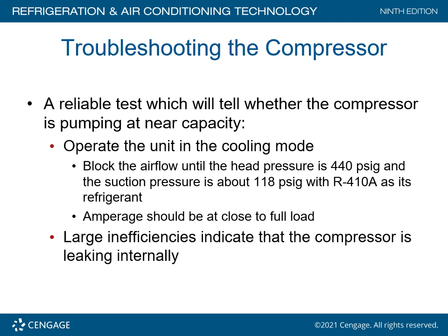A reliable test will tell whether the compressor is pumping at near capacity. Operate the unit in the cooling mode. Block the airflow until the head pressure is 440 PSIG and the suction pressure is about 118 PSIG with R410A as its refrigerant. Amperage should be close to full load amps. Large inefficiencies indicate that the compressor is leaking internally. I will say this, on heat pumps, the compressors are designed to be more tolerant of liquid because you are operating in both heating and cooling mode. The compressors are typically better built.